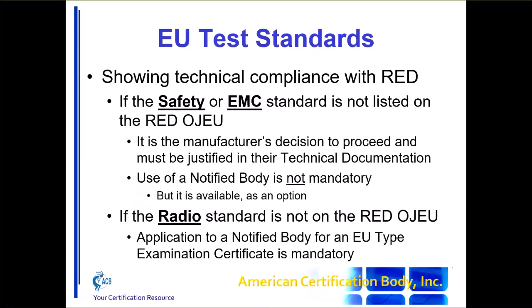Now, one thing I really want to clarify about the harmonized standards: if the safety standard or the EMC standard is not listed on the RED Official Journal of standards, then the manufacturer can still proceed to sign their DOC and they do not need the notified body.